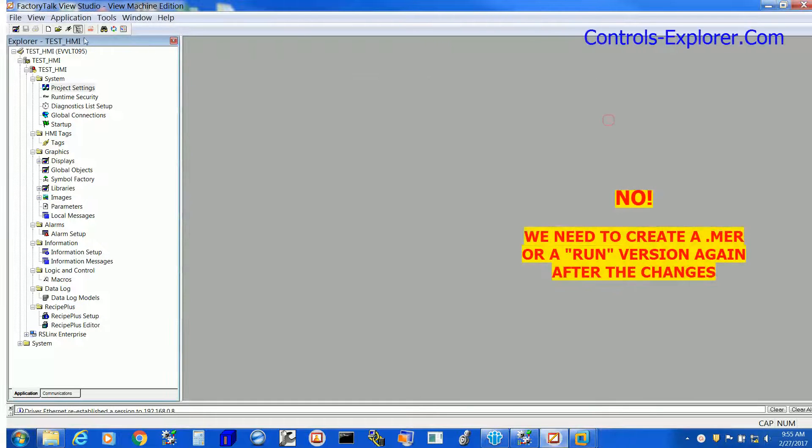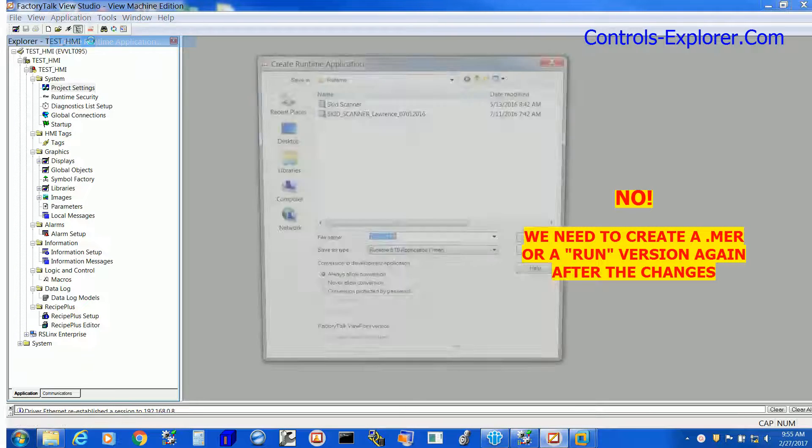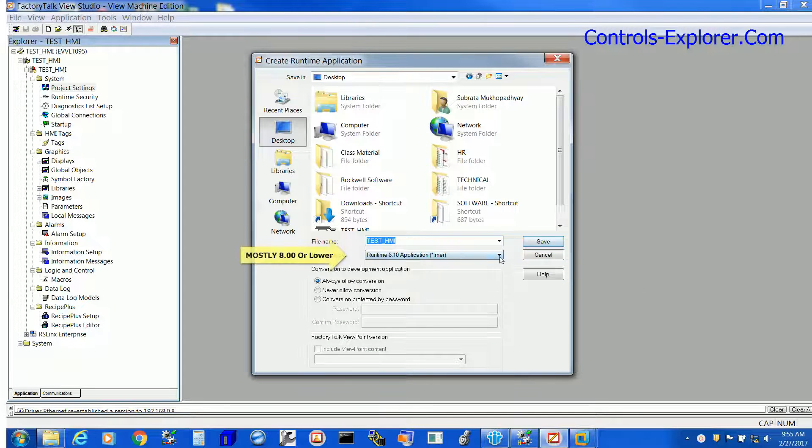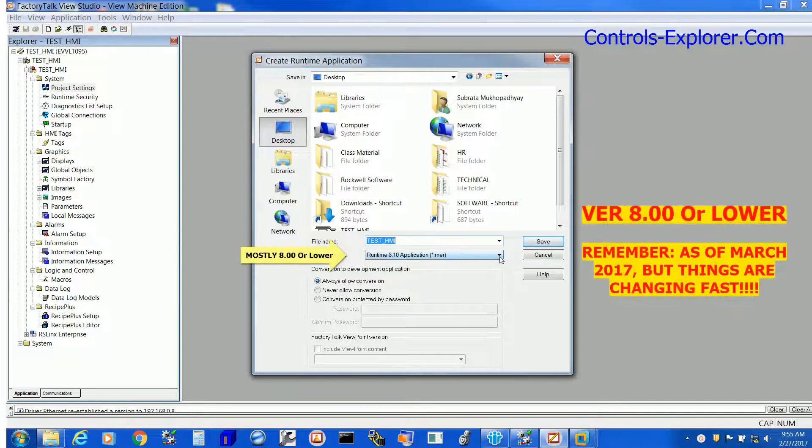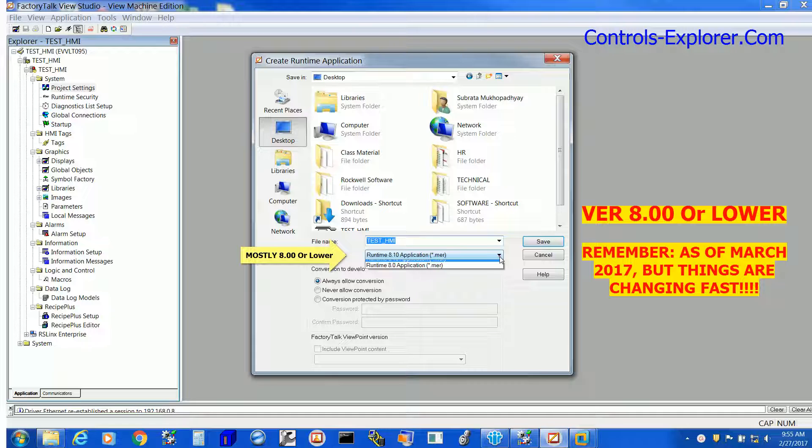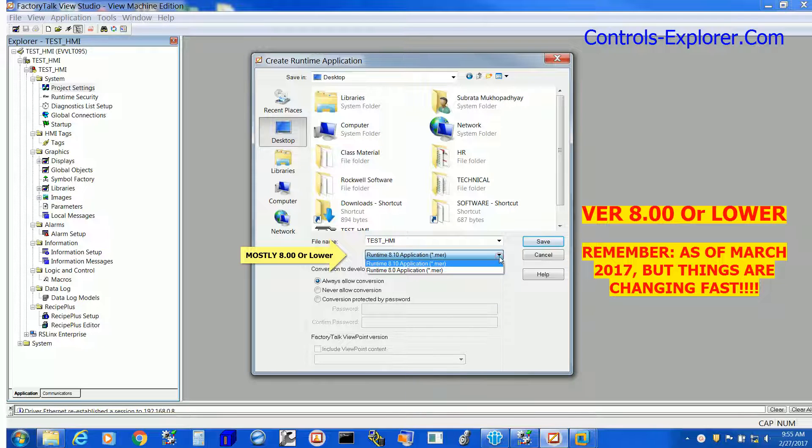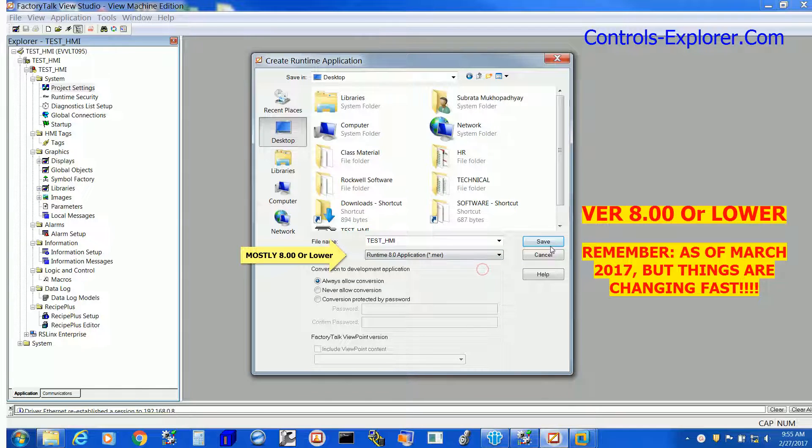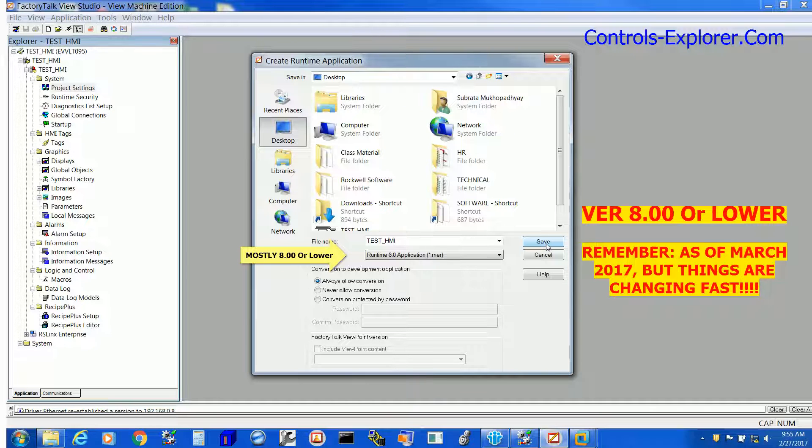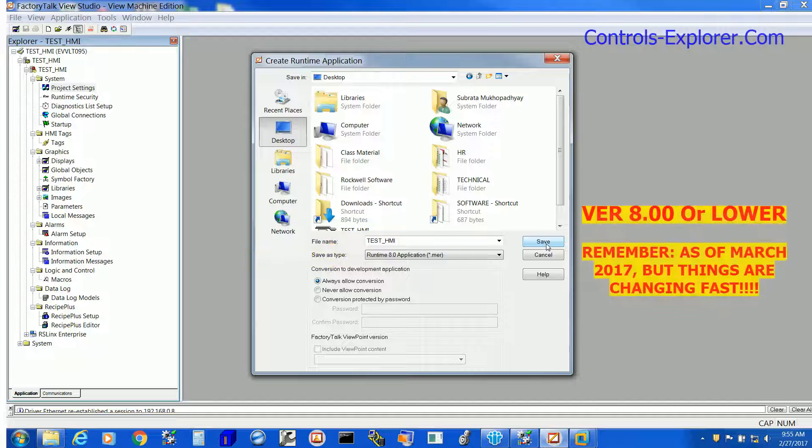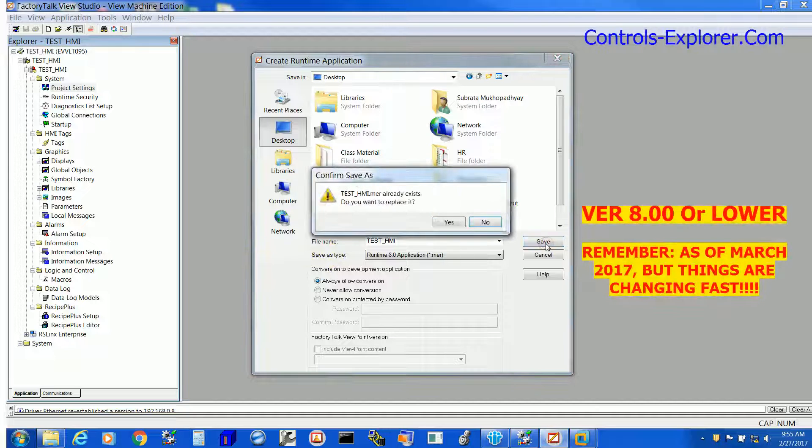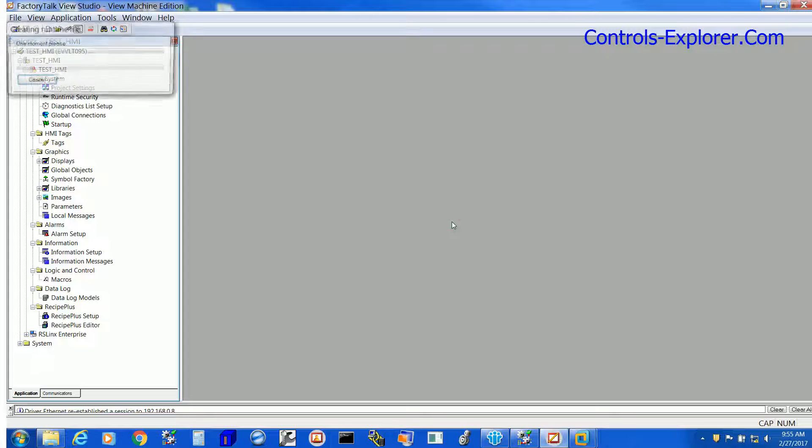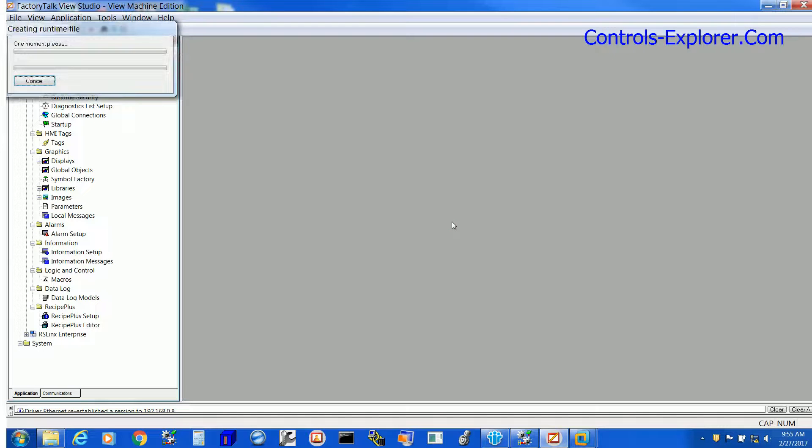So let's create a new .mer or run version of the HMI program, but one thing please note here: as of March 2017, all the Rockwell or Allen Bradley touch screen HMI Panel View Plus are not compatible to any run version if you create above 8.0. So please select the version either 8.0 or lower, whichever suits the HMI what you have. Remember one thing again, as of March 2017. So here we are creating the run or .mer version of this HMI program.